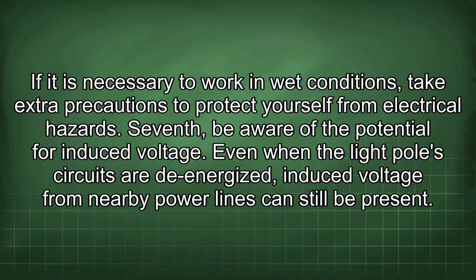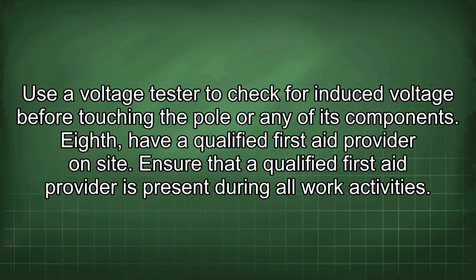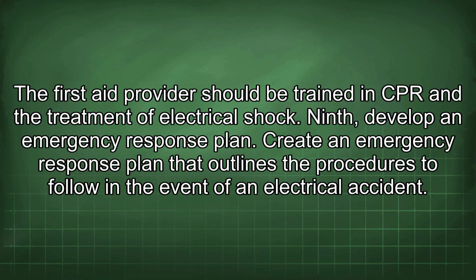Seventh, be aware of the potential for induced voltage. Even when the light pole circuits are de-energized, induced voltage from nearby power lines can still be present. Use a voltage tester to check for induced voltage before touching the pole or any of its components. Eighth, have a qualified first aid provider on site. Ensure that a qualified first aid provider is present during all work activities. The first aid provider should be trained in CPR and the treatment of electrical shock.